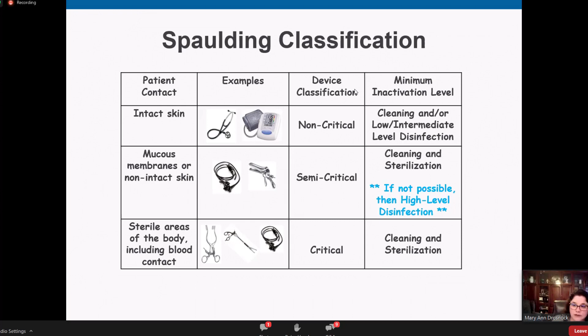Just make sure when you're using a endoscope that you're reprocessing that endoscope per the manufacturer's instructions for that device. And also think about scopes that have been through the process and that you've taken out of the cabinet: we do recommend that those be processed again before use. So you're really doing a quality check of the process itself. Okay, I thought that was important to interject there. I was going to mention that. Thank you.